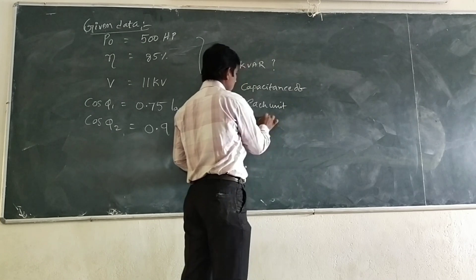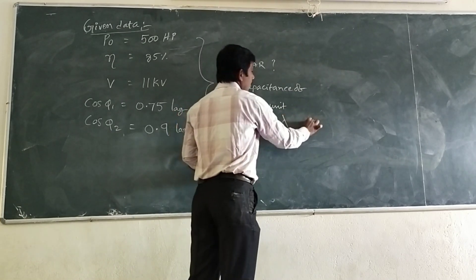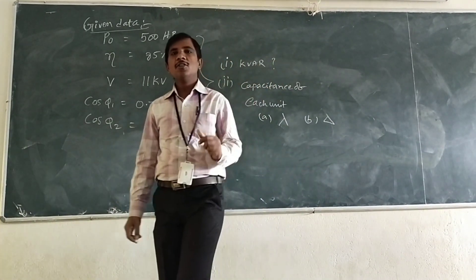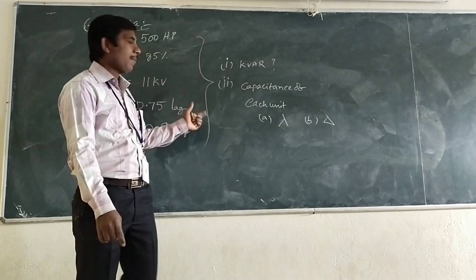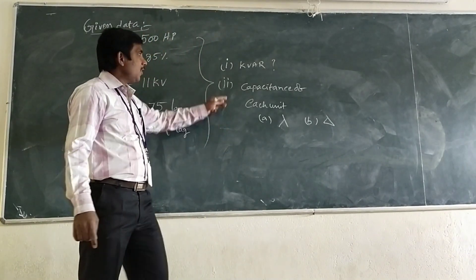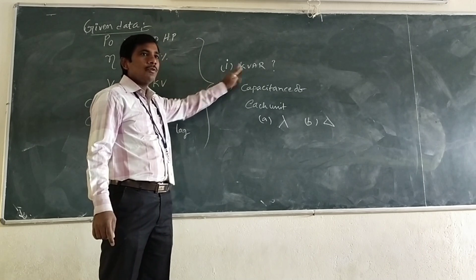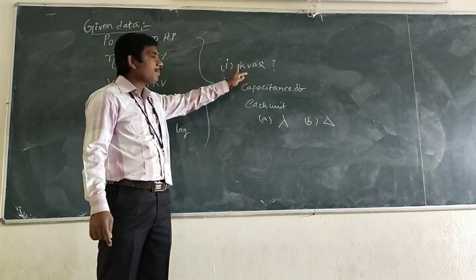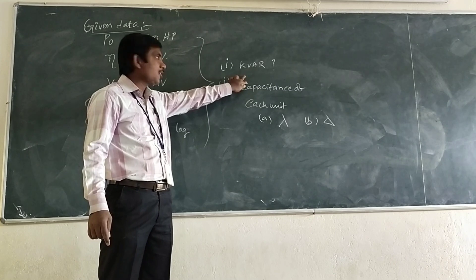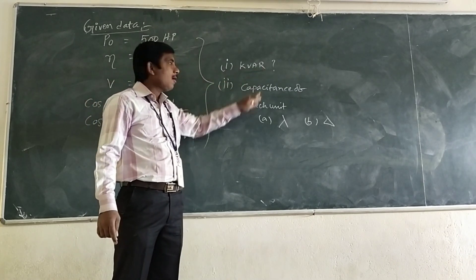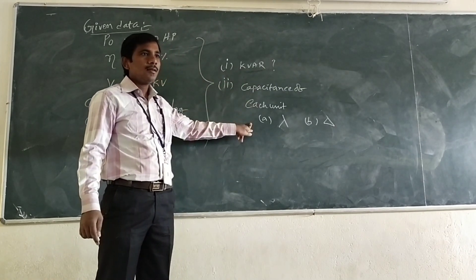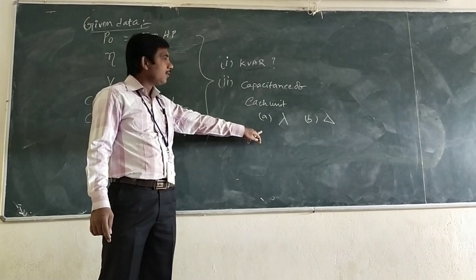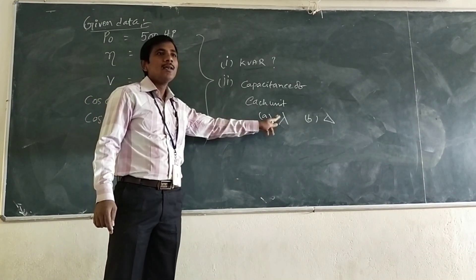When the capacitors are connected in star as well as delta, what is the rating of the capacitor bank required? First, we have to calculate the capacitor rating to improve the power factor using P × (tanφ₁ − tanφ₂). We also need to calculate the capacitance of each unit in microfarads, for both star and delta connections.